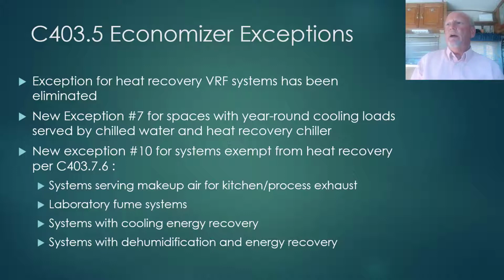The exception for heat recovery VRF systems has been eliminated. That doesn't mean that you now have to provide economizers for VRF systems. We just went through that. So if your VRF, variable refrigerant flow heat pump system, does not include equipment located outdoors or in an equipment room next to outdoors, it does not have to have an economizer. So if it's fan coil units above the ceiling, wall mount units, console units, then an economizer is not required.